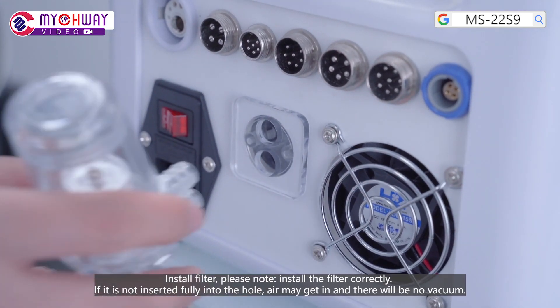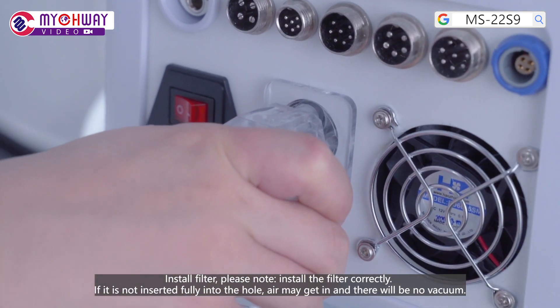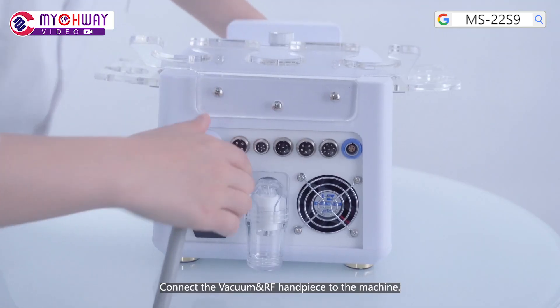Install a filter. Please note: install the filter correctly. If it is not inserted fully into the hole, air may get in and there will be no vacuum. Connect the vacuum and RF handpiece to the machine.